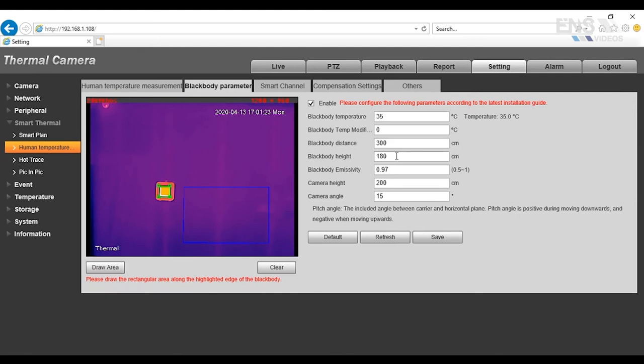The black body height will be from the base of the black body to the ground, so the 180 centimeters will be 1.8 meters. The camera height will be 200 centimeters from the base of the camera to the ground, so that's going to be 2 meters. The camera angle, you can leave a default at 15 degrees and then hit save.